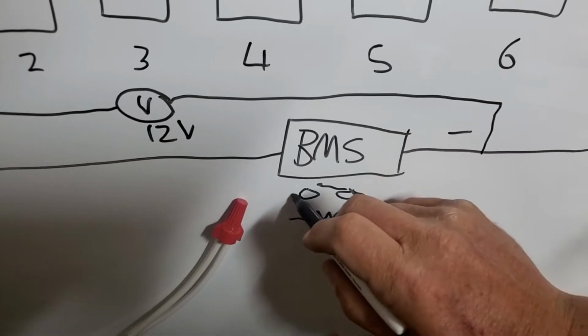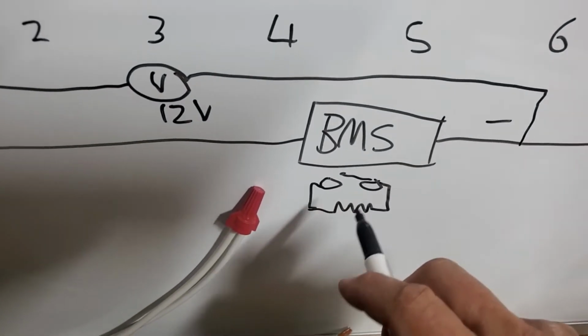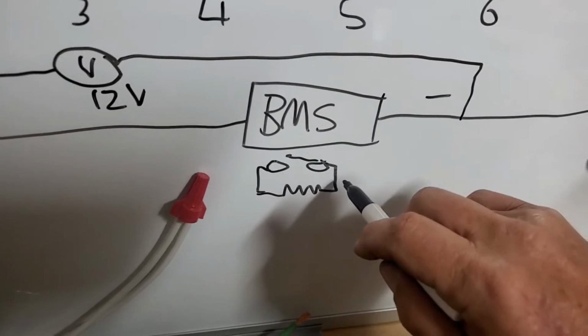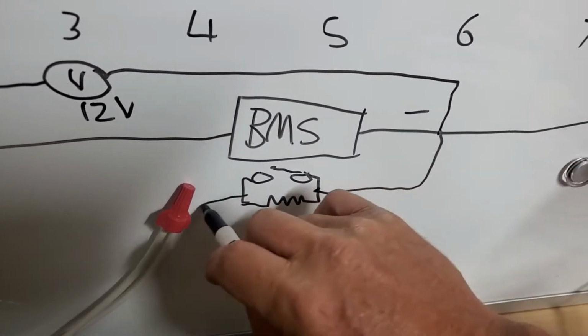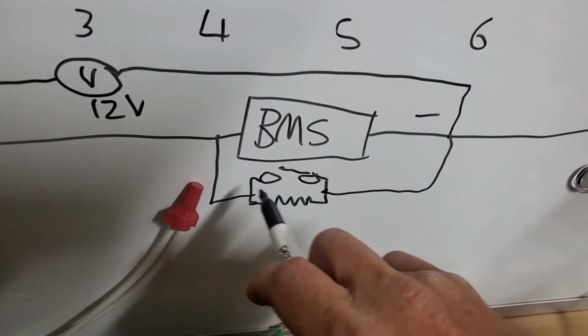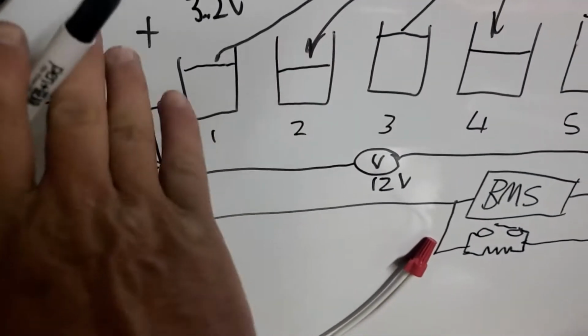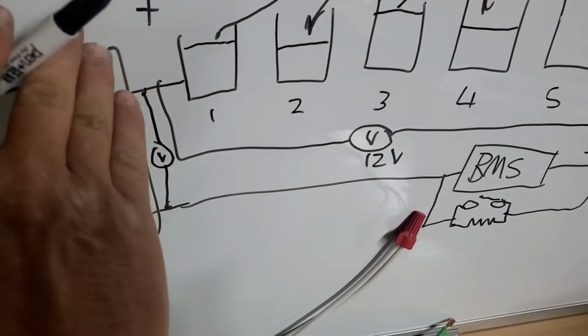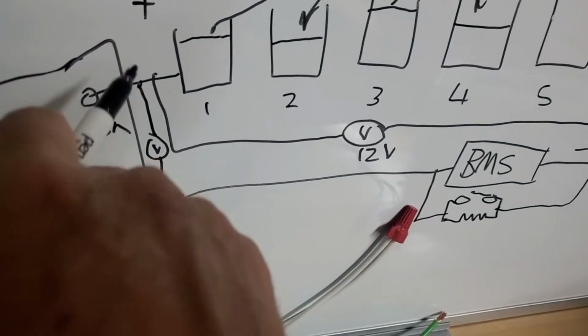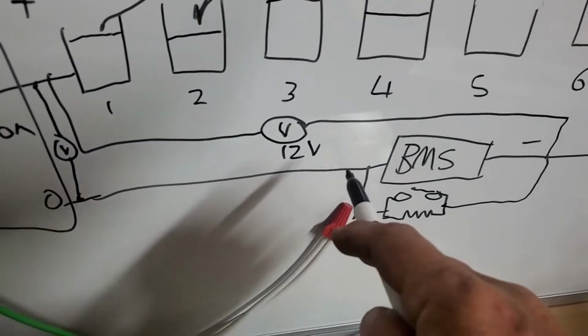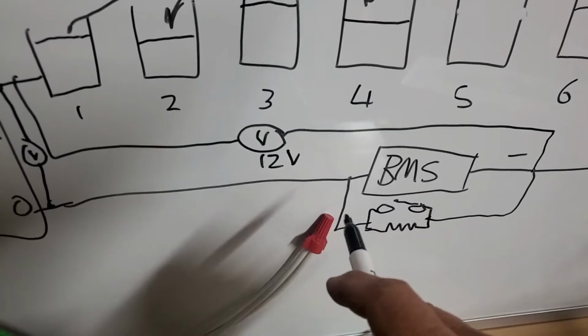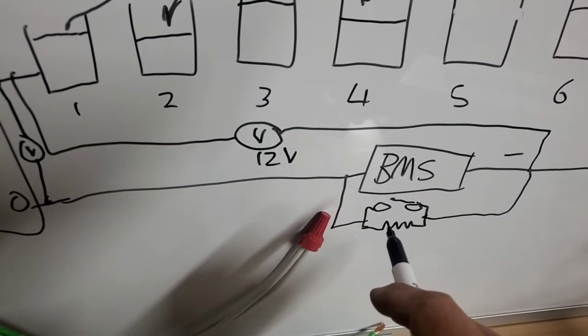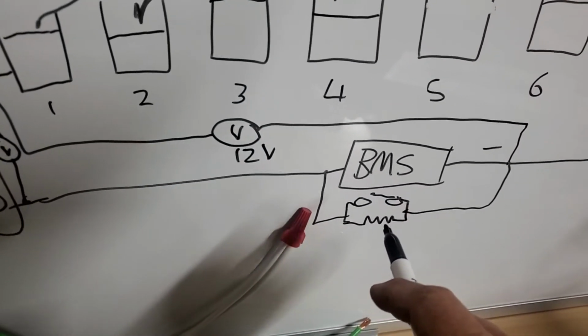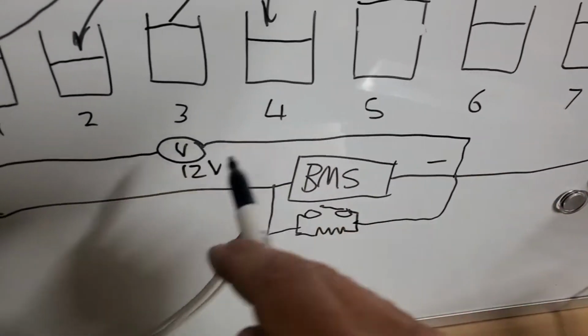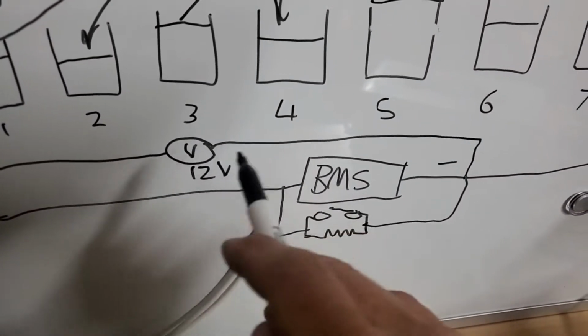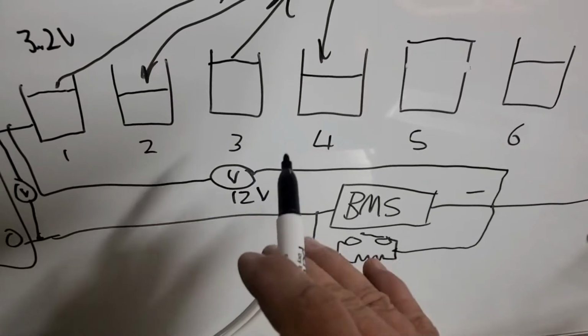That little resistor, even though the big switch trips, is still going to put a voltage through there. If you've got no load on your inverter, and it's disconnected, you're still going to get full battery voltage because you're measuring through that little resistor. Remember, you only get a volt drop if there's current going through a resistor. Your voltmeter doesn't draw any current, so you're measuring basically exactly the same voltage that's on your battery. It's going to confuse you.